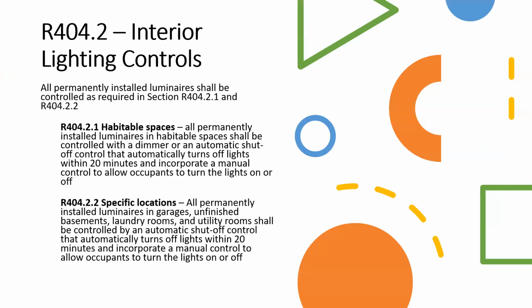And then lighting controls for that is for interior. It says all permanently installed luminaires shall be controlled as required by these sections. Now, these are the two new ones, habitable spaces and specific locations. Before it just said it had to have lighting controls, but now it breaks it into habitable space and specific cases. So all permanently installed luminaires in habitable spaces shall be controlled with a dimmer or automatic shutoff that automatically turns off within 20 minutes, and incorporate a manual control that allows occupants to turn lights off and on.